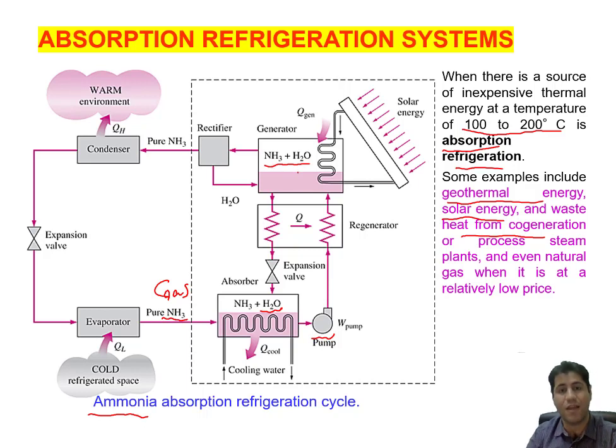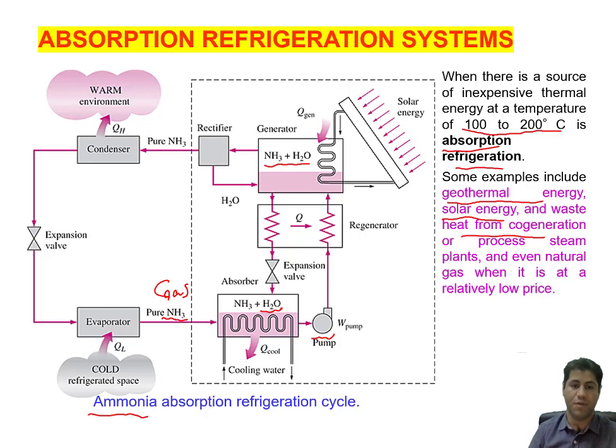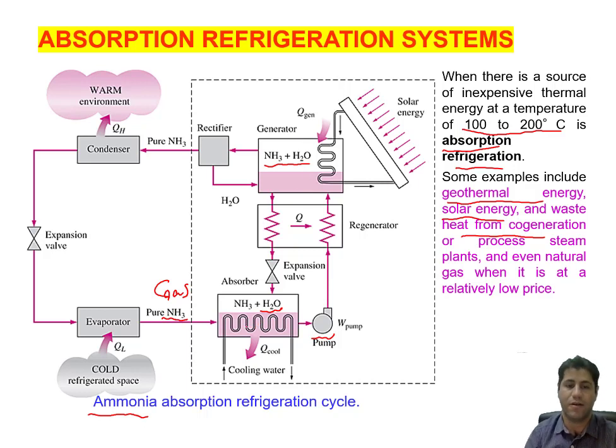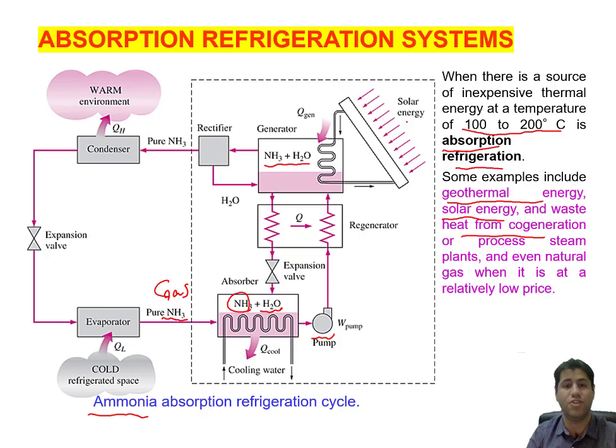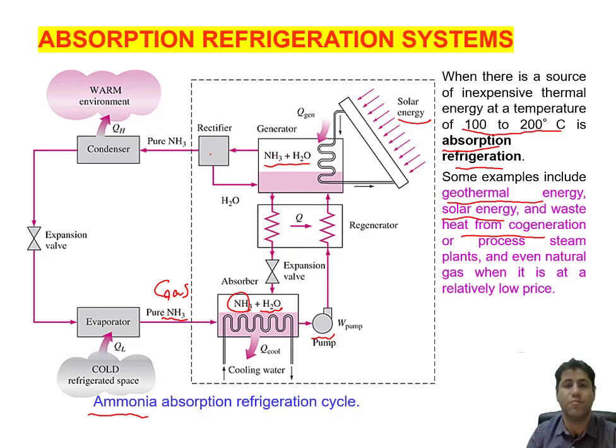In the generator, the temperature of the NH₃ plus H₂O mixture is increased. Due to this temperature increase, the ammonia separates from the water. The reason is that at lower temperatures, more ammonia is willing to dissolve in water — so at higher temperatures, ammonia comes out of solution. In the absorber we have low temperature, and more ammonia dissolves. Once it reaches the generator, the temperature is raised by the thermal energy source, and ammonia separates from water.